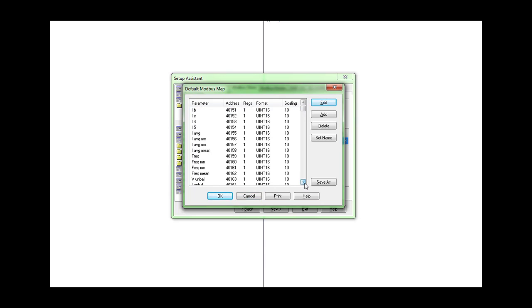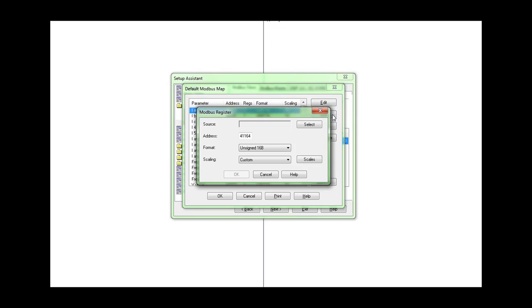So what we are seeing right now is the default Modbus map, and if you compare the list we are looking at with the PDF, it is exactly the same. We can see the current, the voltage, and the energy values, but we cannot see the harmonic values. So what we need to do is click on the Add button. Now we can see a small window asking for the source or the variable that we need to add to this Modbus map.